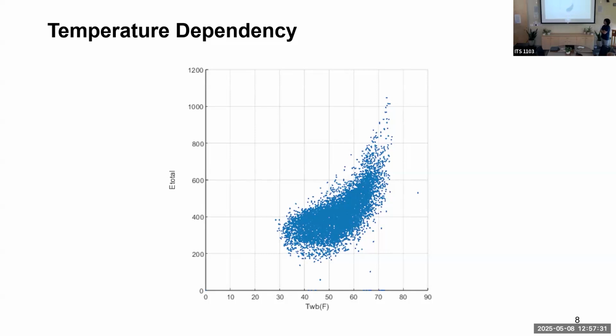Yeah, we've looked at it. Another big factor is what their production looks like. When is their product coming in and going out? Those are the periods when your cooling demand would go up. That gets translated into time of day and then day of the week. If they're operating on weekdays and not on weekends, then you would see that difference. And if their product is only coming in from 6 to 3, then you would see a higher cooling load between that 6 to 3 period than the later hours. So there is another big correlation with their production schedules.